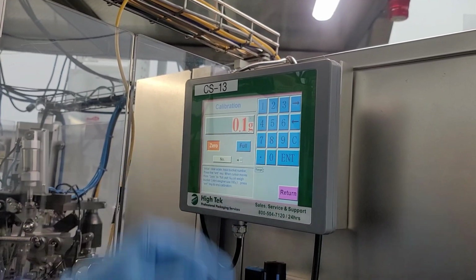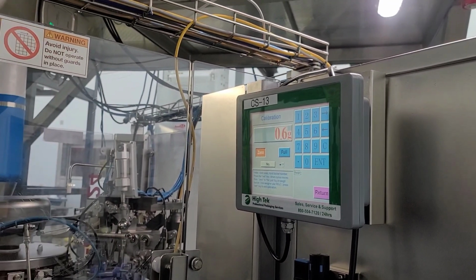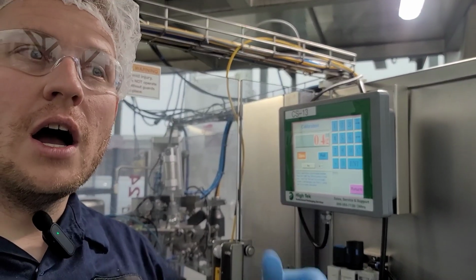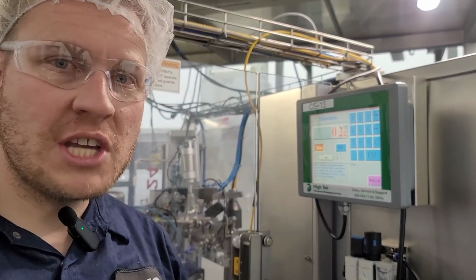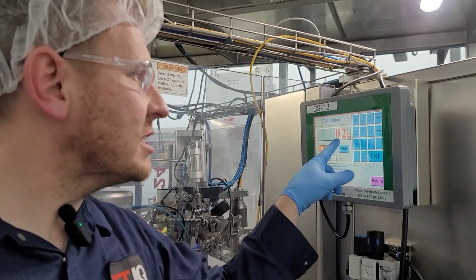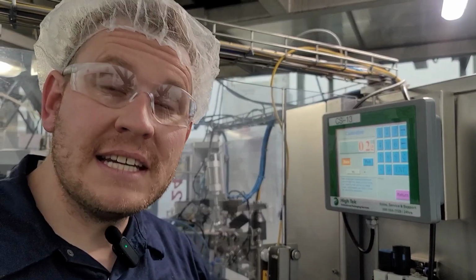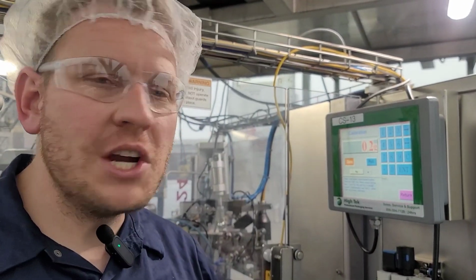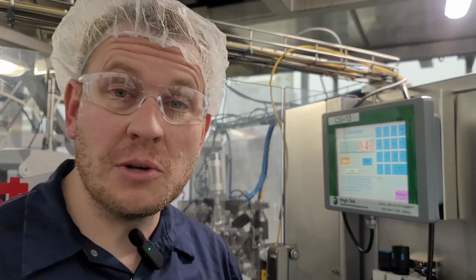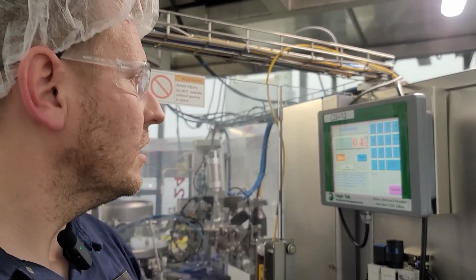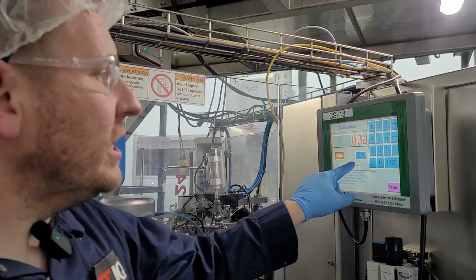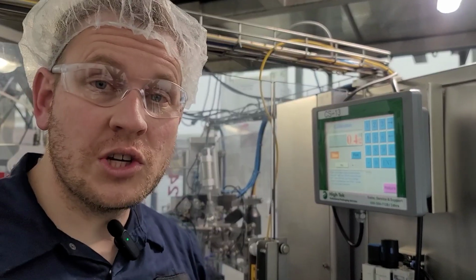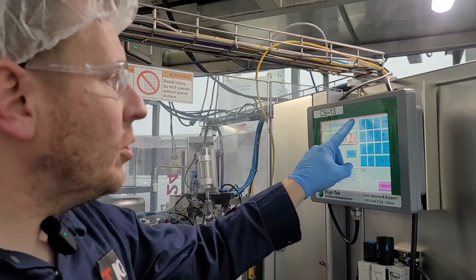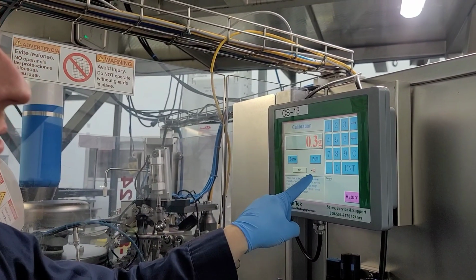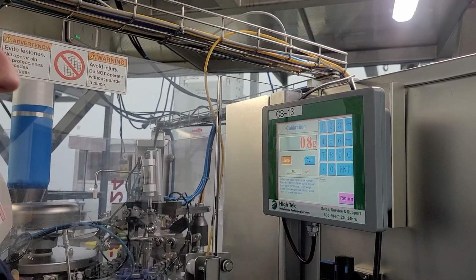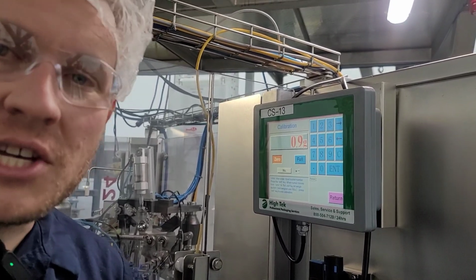This fluctuation occurs with the sensitivity of the load cell. Air conditioning blowing on the load cell can make this fluctuate like this. Walking on the mezzanine, any type of vibration can cause this. This is normal and to be expected. Once the calibration is complete, if you have others to calibrate, you simply input the next number, press enter, and repeat the process.